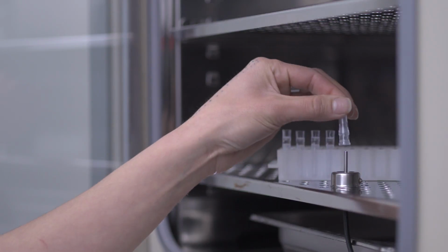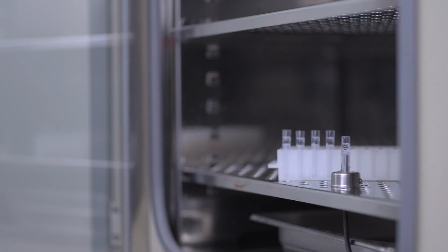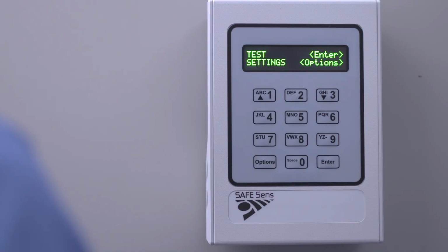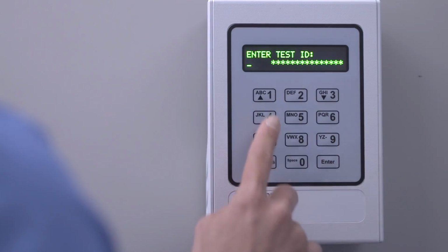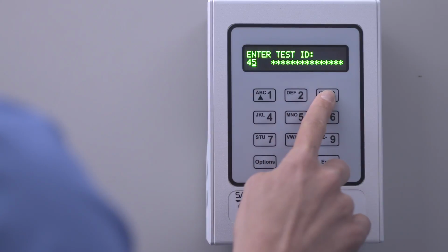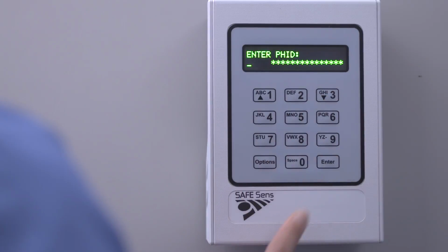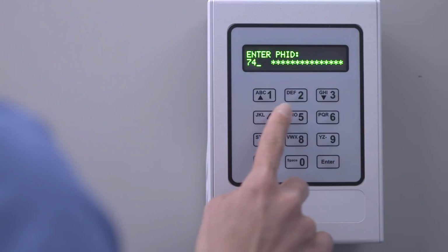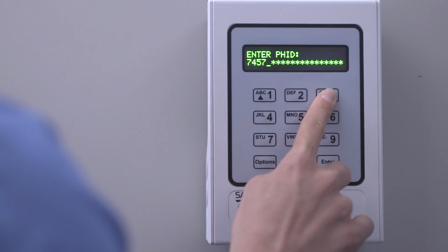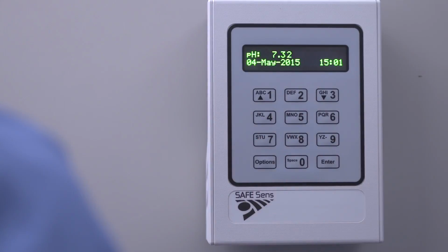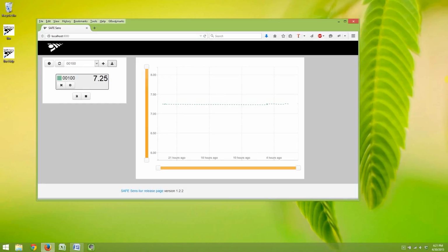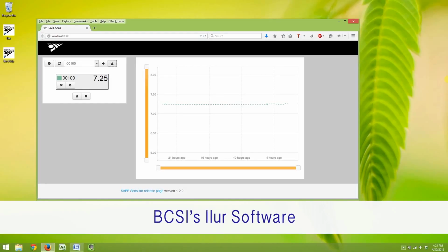We can place one of the sensors onto the probe in the incubator and begin monitoring the pH for the next 7 days. Simply start a new test by typing in a unique ID number and the appropriate pH ID. It is important to change the ID number with each new pH sensor being monitored.